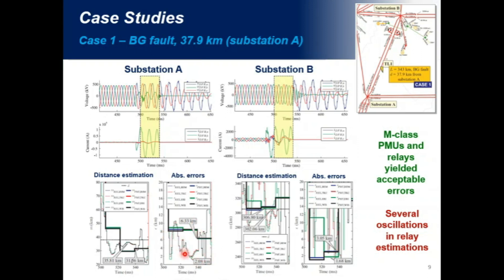However, analyzing the substation B here, we could see that signals have presented a lot of oscillations during the fault location. So, we considered in this paper the average value during that period. And regarding the errors, we could see that both relay and PMU fault locations were presented an accuracy within the accepted margin of about three and two kilometers, approximately. So, the good thing is that M-class PMUs has shown to be capable of estimating fault distance. They yielded acceptable errors, but several oscillations were verified in relay estimations.